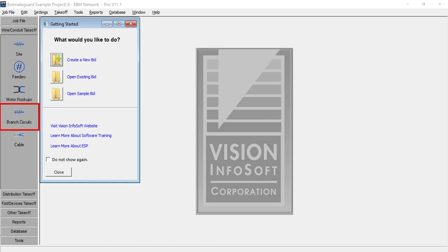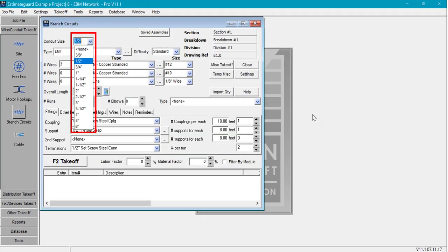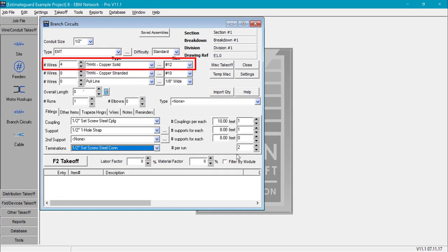We'll select Wire Conduit Takeoff to begin our estimate. We'll select Branch Circuits, Conduit Size, Difficulty, Conduit Type, Wire Type, Size, and Count. Typically as an estimator you would set this as three wires, take off all the half inch EMT on the project that contains three wires, then set it at four wires, take off all the conduits that contain four wires, then do the same for five wires which will include a ground. This will give you a more accurate wire count.